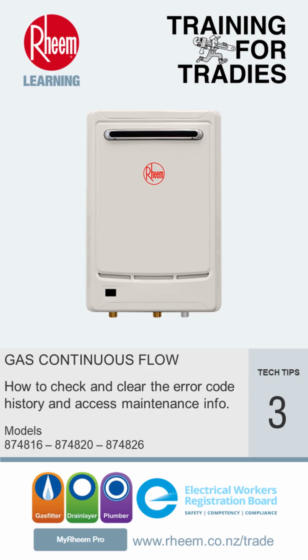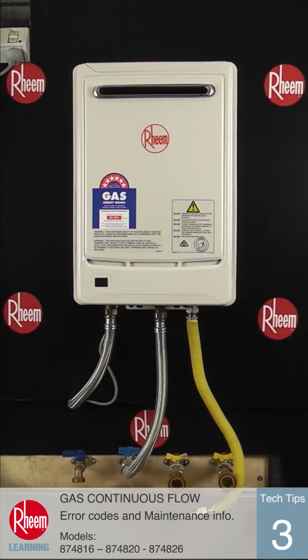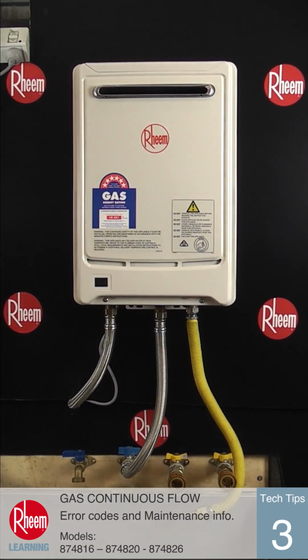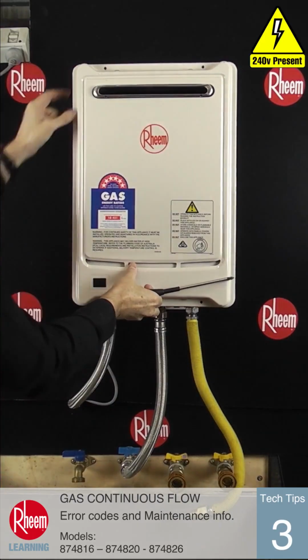This time we're going to show how to check and clear the error code history and access the unit's maintenance information on Rheem Series 2 gas continuous flow water heaters. The current error code will be displayed on Rheem gas continuous flow water heaters and controllers, but the last 8 error codes are saved into memory.